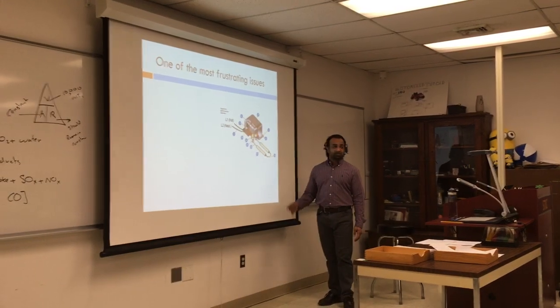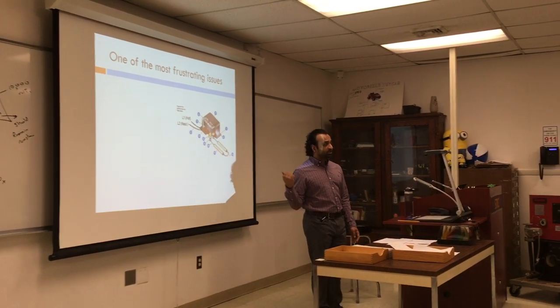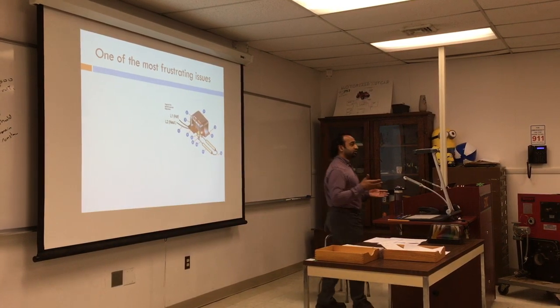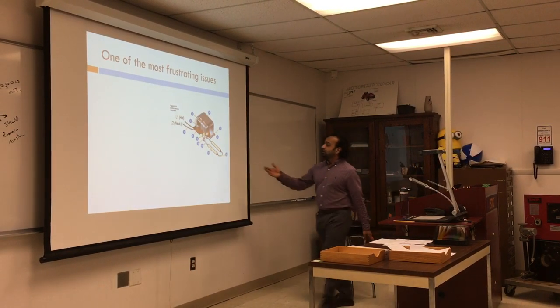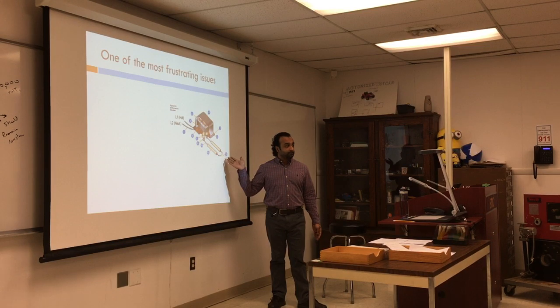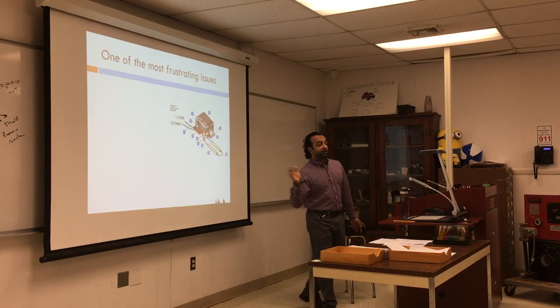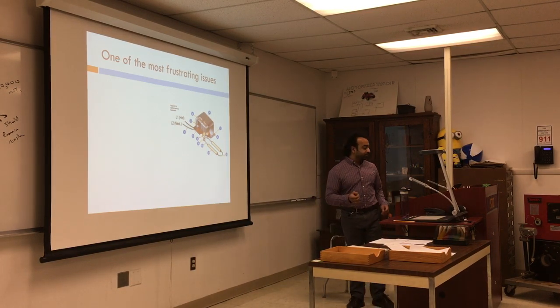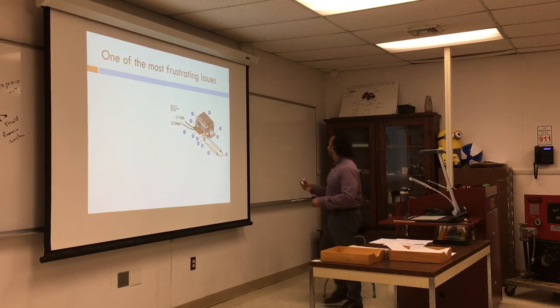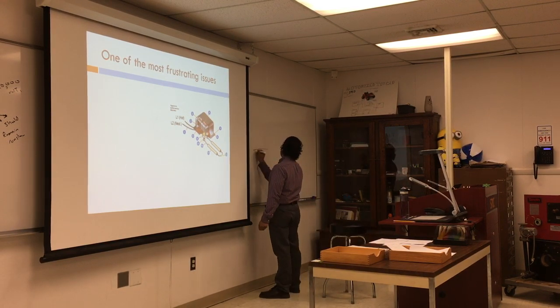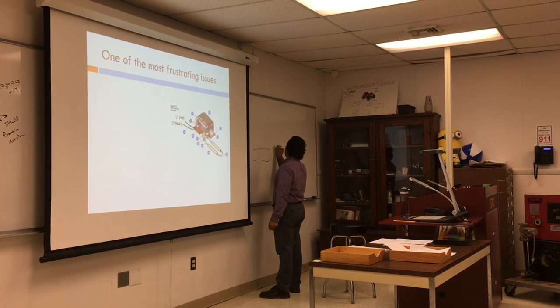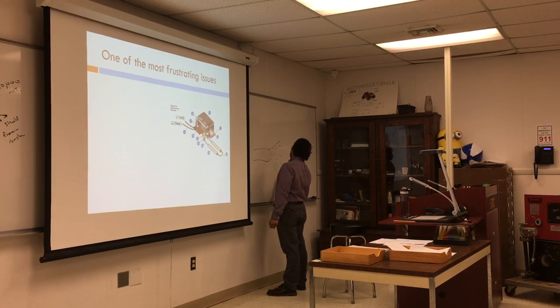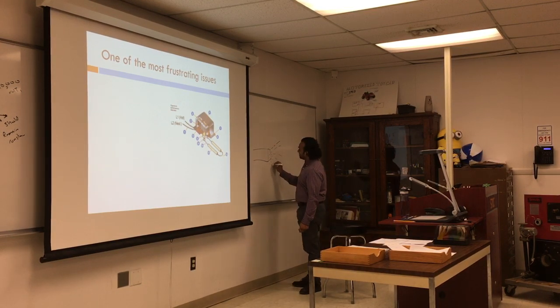And sometimes the spray angle has changed since the design, and you have too much oil covering the electrodes so it does not ignite. That's why it's very important to put the ignition in the right location of the spray pattern. If this is your nozzle and it's spraying, again, this area has more density of oil than this area.